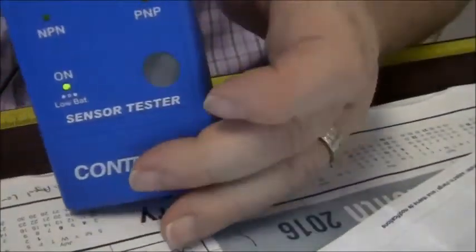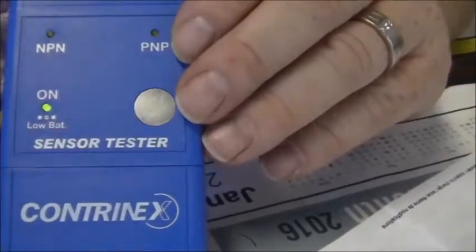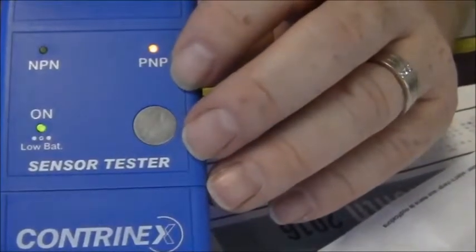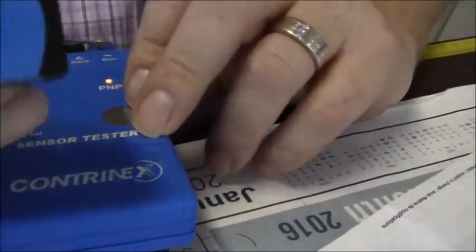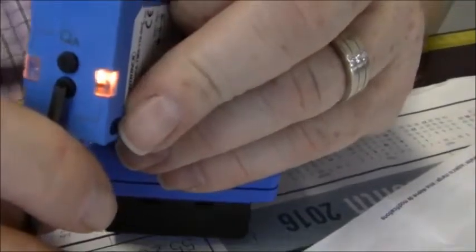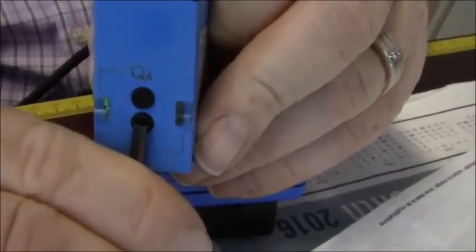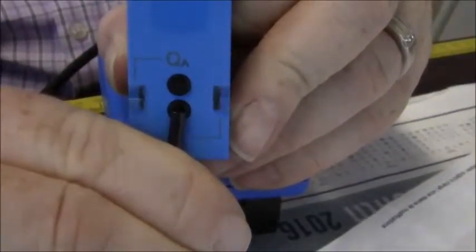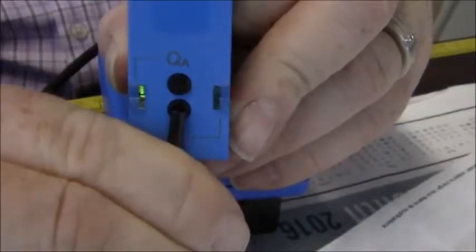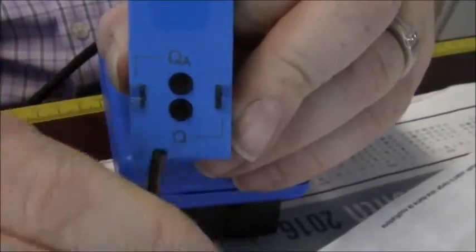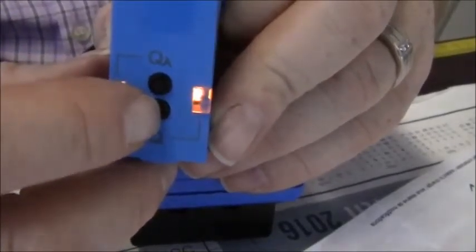You'll see right now that it's set up on PNP. What I can do is press and hold this Q. I'm supposed to hold it for greater than 13 seconds. The yellow and green will flash at the same time. When I let go, they both flash at the same time. If I press it once, I've taken it out of PNP into NPN.